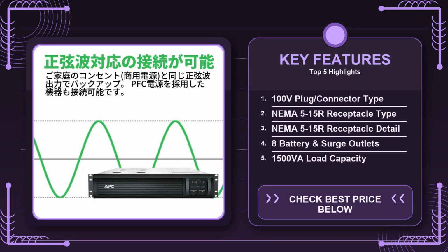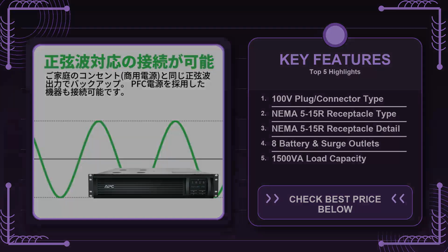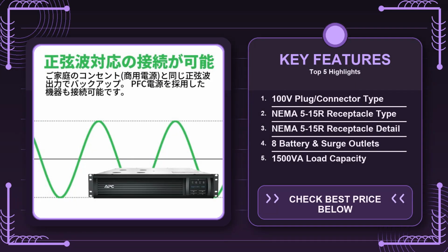Another real-world perk is the configuration of outlets. The 1500 LCD-RM ships with a mix of battery-backed and surge-only receptacles. The battery-backed outlets are grouped together, making it easy to plug in the most critical devices like your server's power supply and network switches, while the surge-only outlets can handle peripherals that don't need backup, such as a monitor or a printer. That separation prevents you from unintentionally draining the battery on a non-essential piece of equipment, which is a mistake some first-time UPS buyers make.